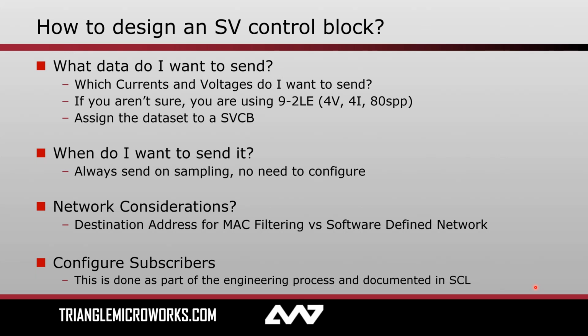So what do you have to keep in mind? Well, if you aren't sure whether you're using 92LE or 61869-9, then you're probably using 92LE. It's well established and supported by just about every vendor that supports sample values. So it's really a matter of deciding which currents and which voltages you want to include. I don't mean how many, I just mean that if you look at the topology of your substation, decide where you want your merging unit, three phase currents and voltages plus neutral for each, and assign that to a specific sample value control block data set and control block. Again, just like GOOSE, we don't have to make any decisions about how often we want to send. Messages are always sent on sampling, and there's no T-min and T-max time like we have with GOOSE.